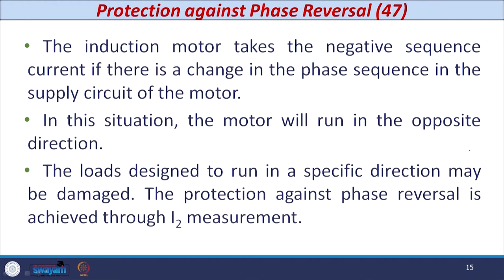The next type of protection is against phase reversal. Instead of giving RYB phase sequence, if the phase sequence is altered or changed, the motor needs to be protected. The relay number given to this protective device is 47. The induction motor takes negative sequence current if there is a change in the phase sequence in the supply circuit. In this situation, the motor will run in the opposite direction, and since the loads connected to the motor are designed to run in a specific direction only, they will be damaged if the motor runs in reverse. Protection against phase reversal is achieved with the measurement of negative phase sequence current I2.